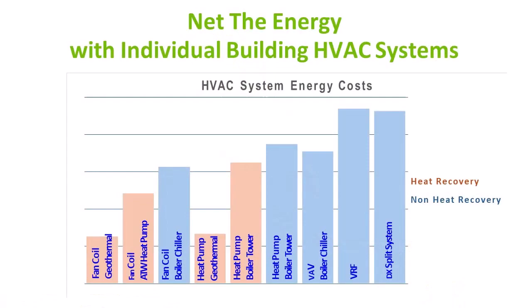To give you an idea, here's a heat pump boiler tower with heat recovery, and here's one without heat recovery. So the heat recovery is worth, what do you think, maybe 15% of the total energy consumption? We can reduce your energy consumption by about 15% by reusing the heat in the building. And again, we model all that with this software.